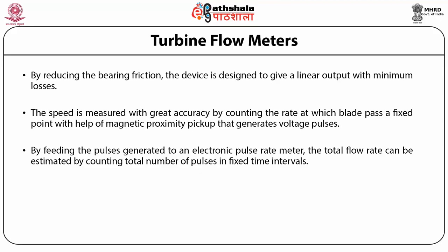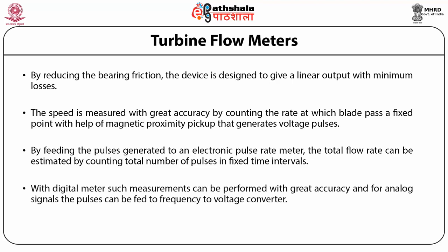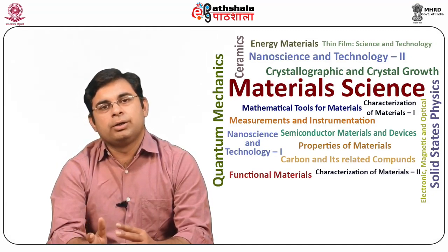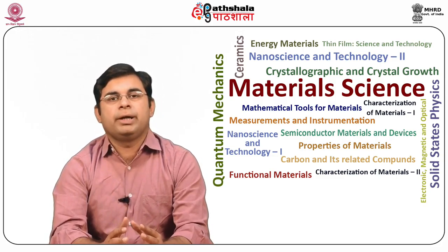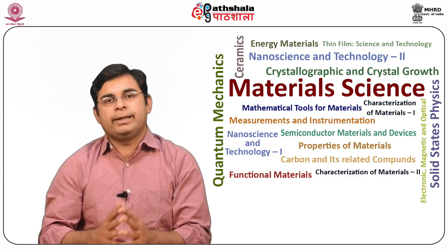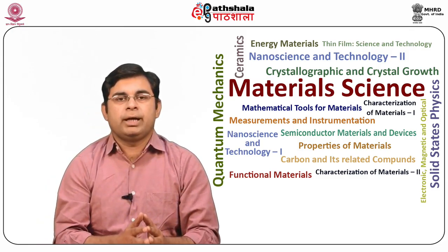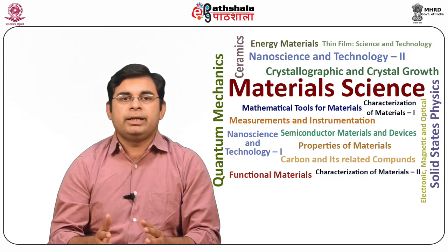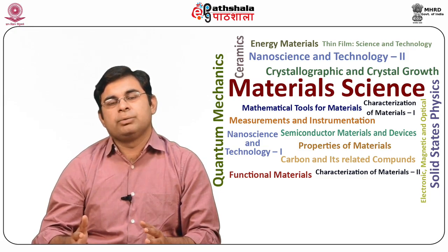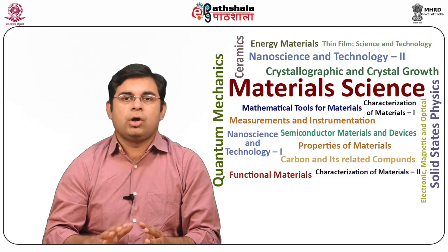By feeding the pulses generated to an electronic pulse rate meter, the total flow rate can be estimated by counting the total number of pulses in fixed time intervals. With a digital meter, such measurements can be performed with great accuracy; for analog signals, the pulses can be fed to a frequency-to-voltage converter. Turbine flow meters are the most commonly used types of flow meter. They provide a direct means to measure both liquid and gas flow rates, are used in remote monitoring and aircraft applications, and have very good linearity of ±0.25% of full scale.